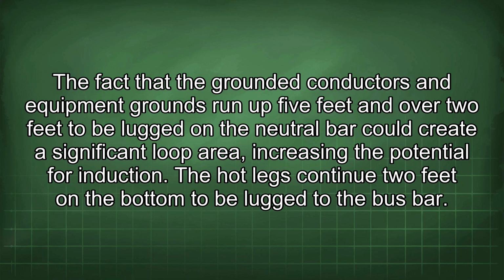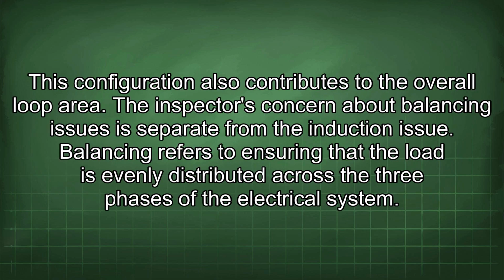The fact that the grounded conductors and equipment grounds run up 5 feet and over 2 feet to be lugged in the neutral bar could create a significant loop area, increasing the potential for induction. The hot legs continue 2 feet on the bottom to be lugged to the bus bar. This configuration also contributes to the overall loop area.